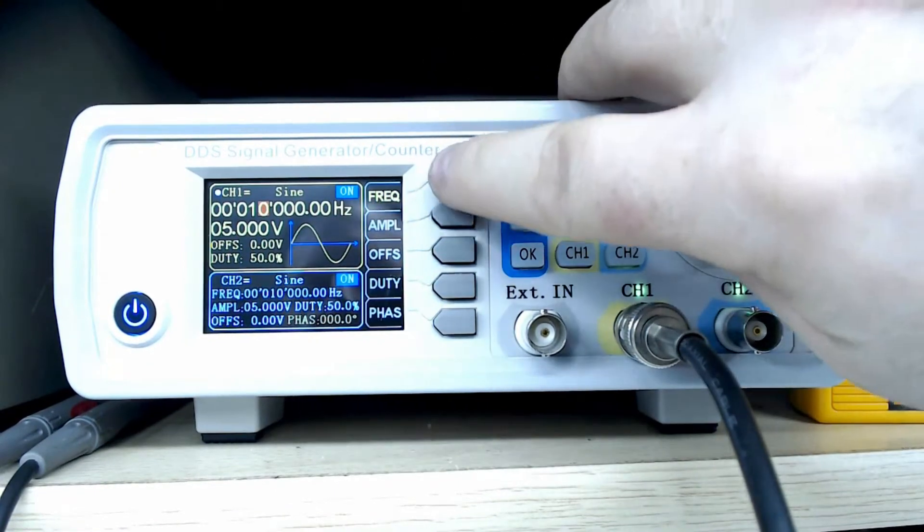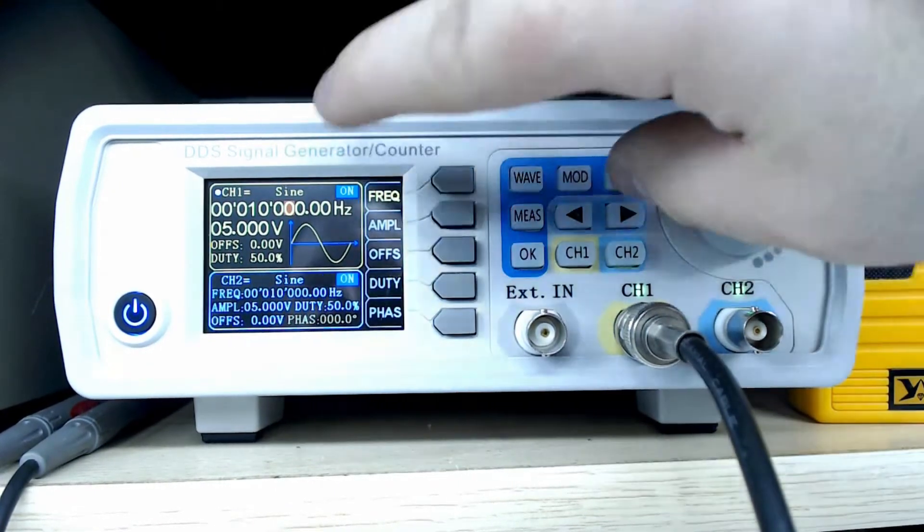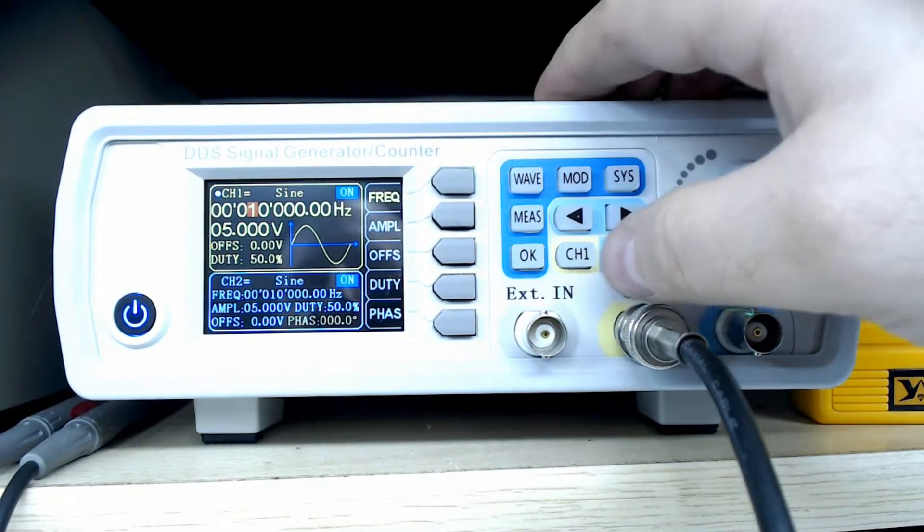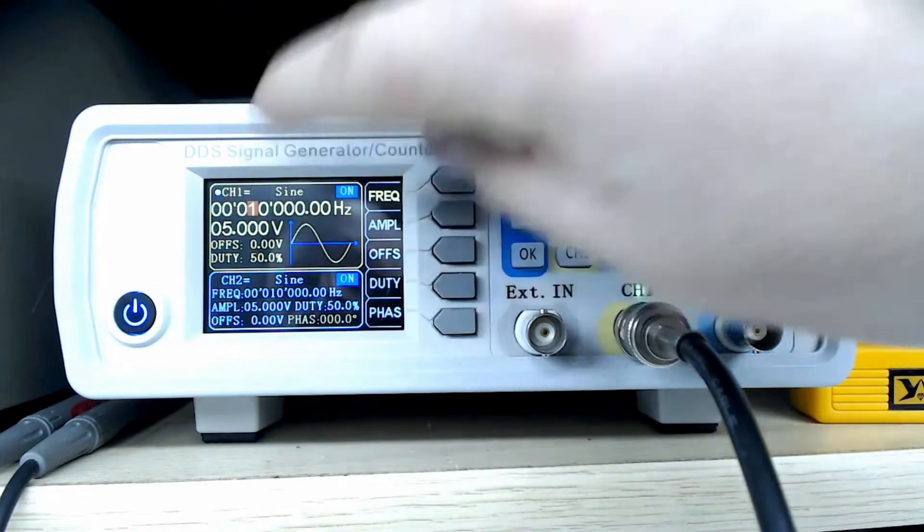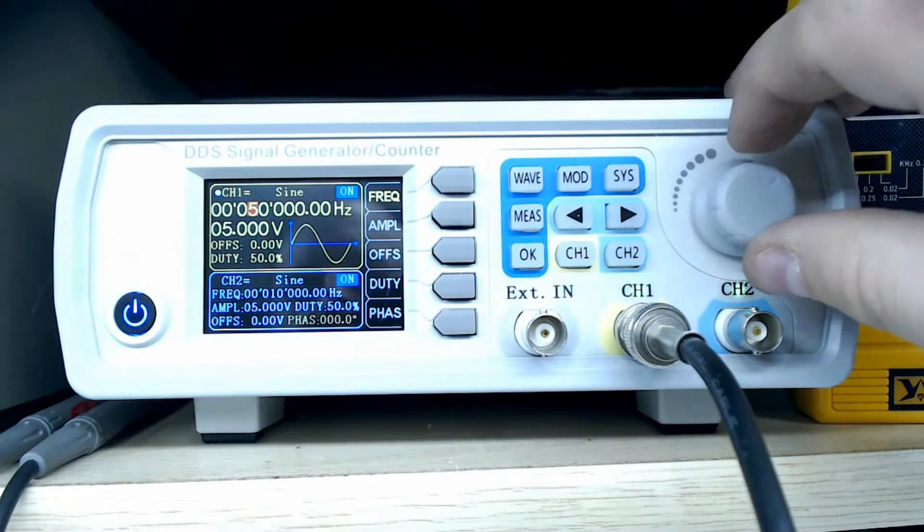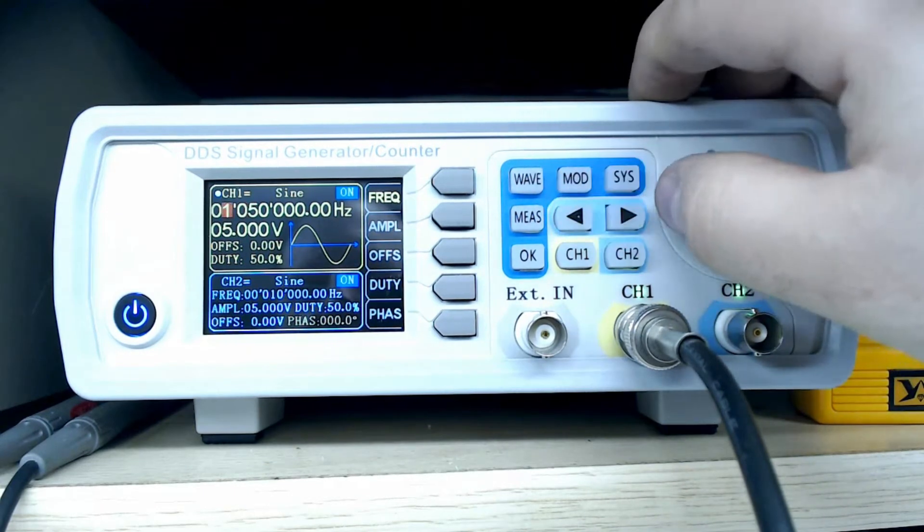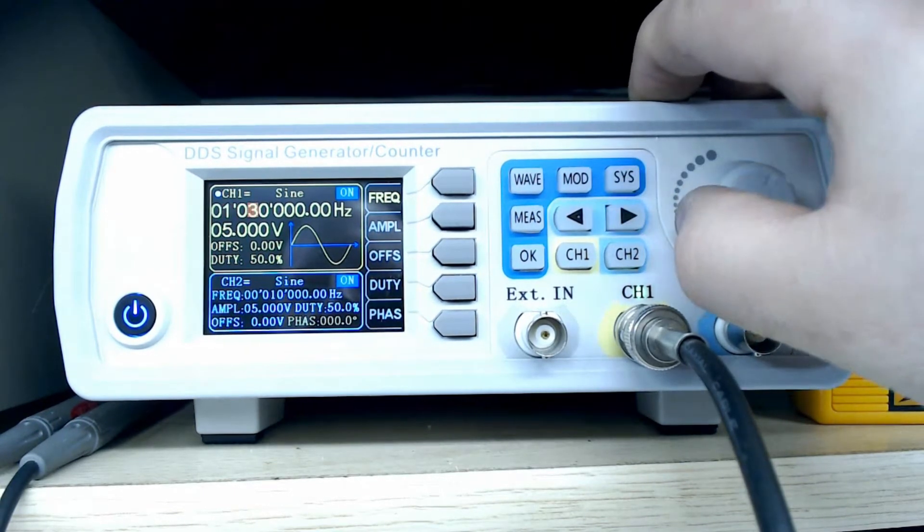If you want to change the frequency, press this, then you use this to move the cursor around. You can see the red selection. So if I wanted to make this 50 kilohertz, I move it to here, select the one and turn the knob. So now I'm at 50 kilohertz. Or if I want 100 kilohertz, say one megahertz, go up to one and go down here like this and now we're at one megahertz.